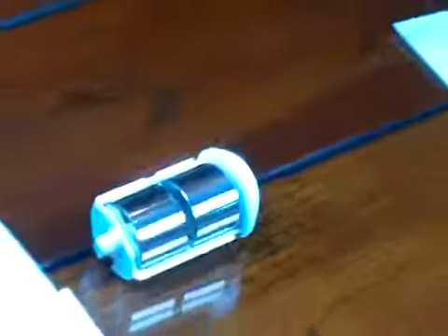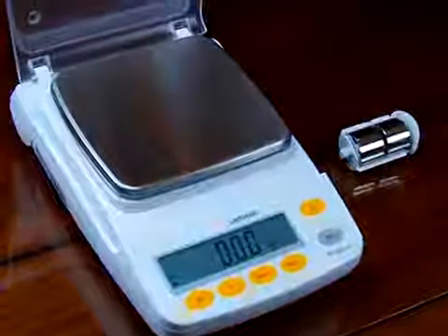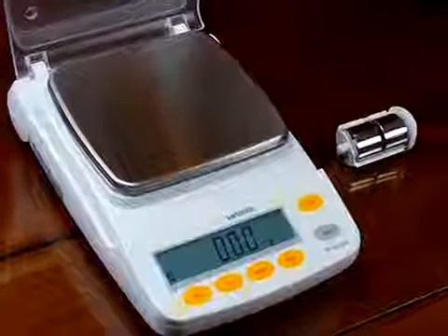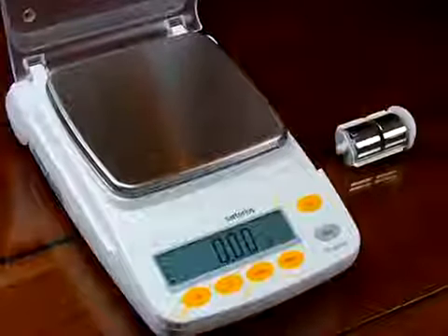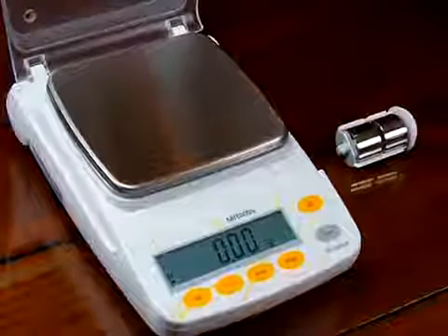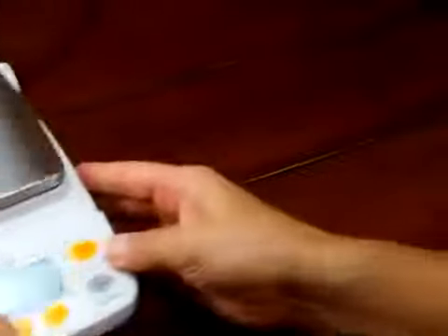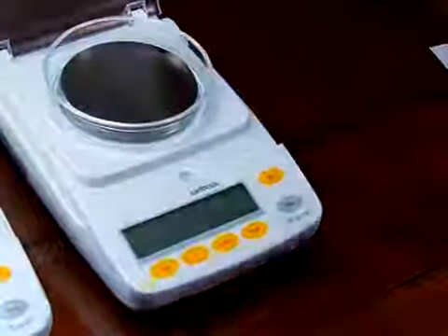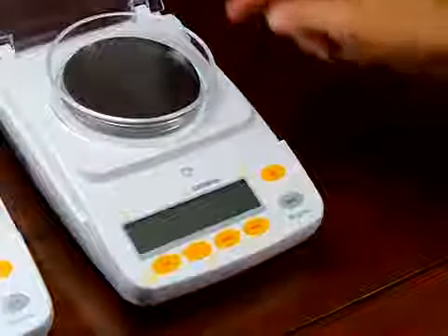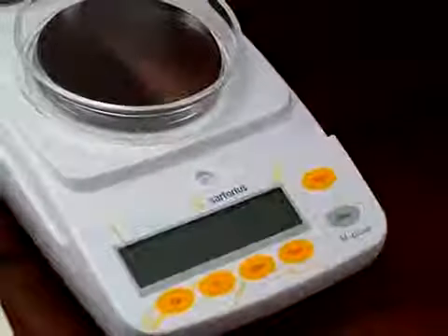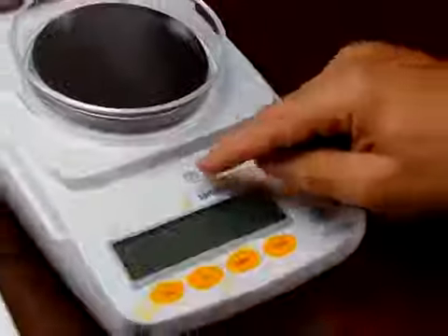Now, your balance should be level when you do your calibration. The only balances in the AY series that come with adjustable feet and a spirit bubble are the AY 123 and 303. So I'm just going to move this scale aside for a minute and show you the model. This is an AY 303. You can tell it has a smaller weighing pan and it has this little glass draft shield. But what I wanted to show you is, number one, you'll notice there's a spirit bubble right in the center of the scale for leveling the balance. And also on the AY 123 and 303, there are 4 adjustable feet.